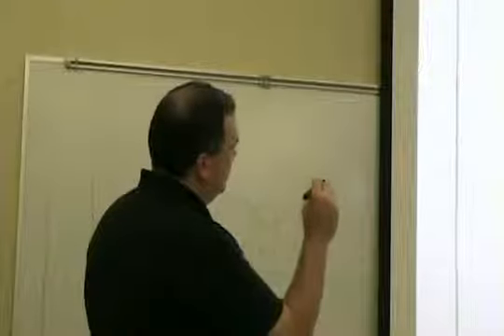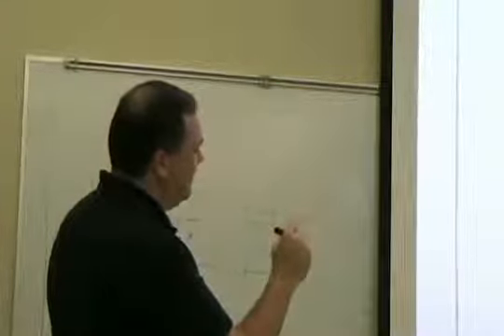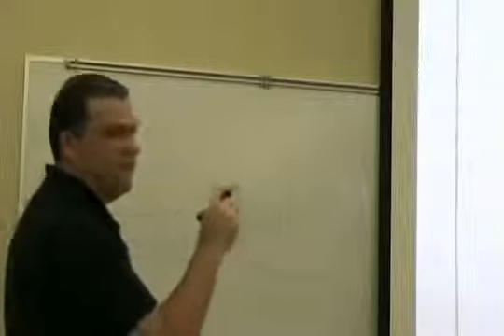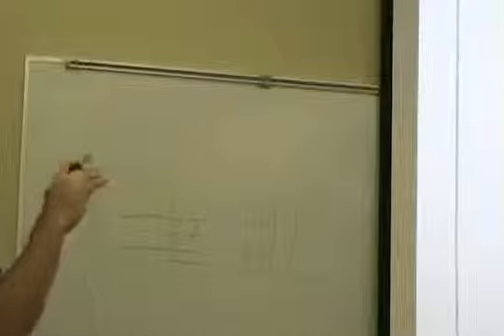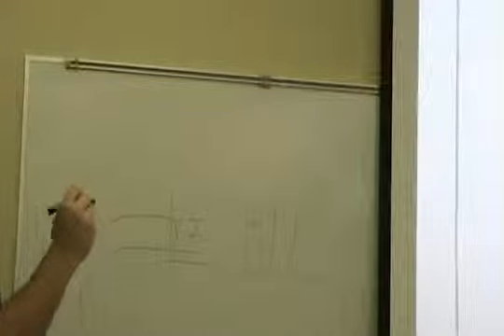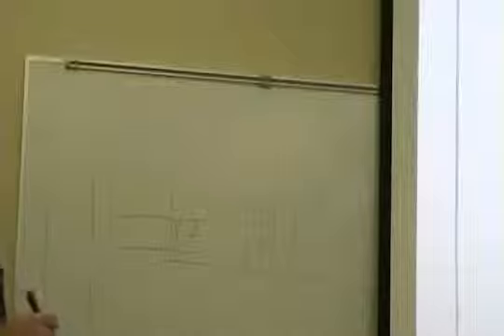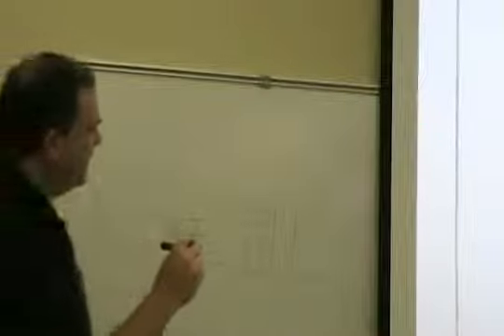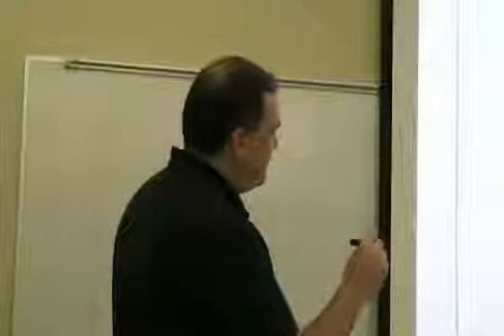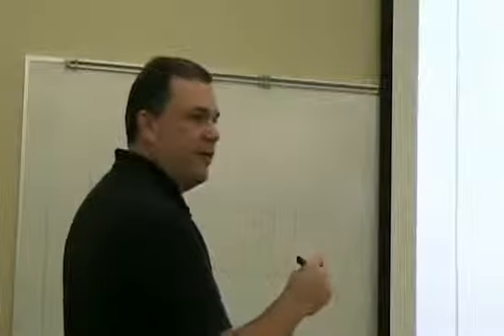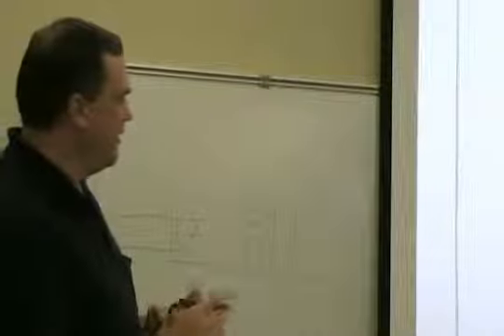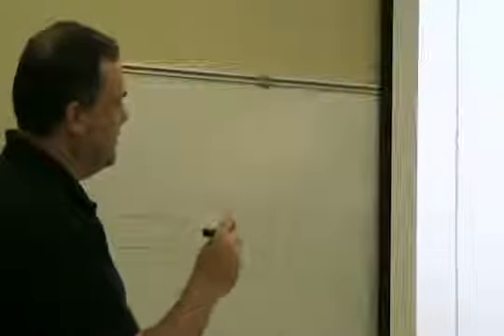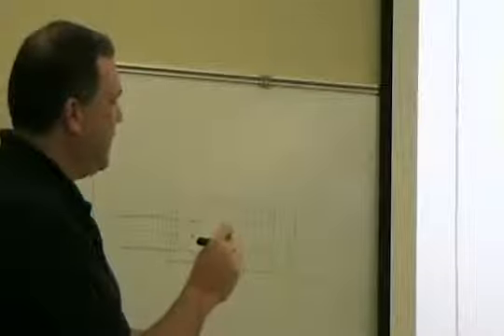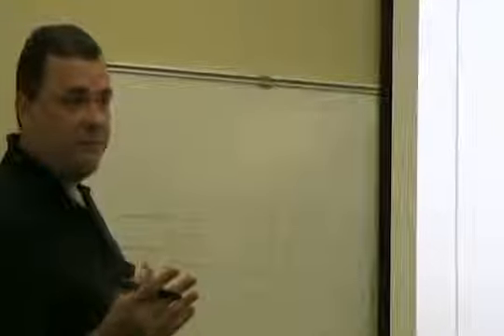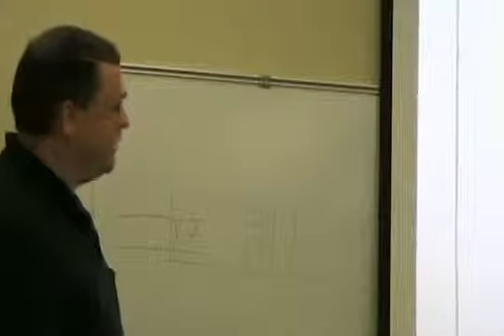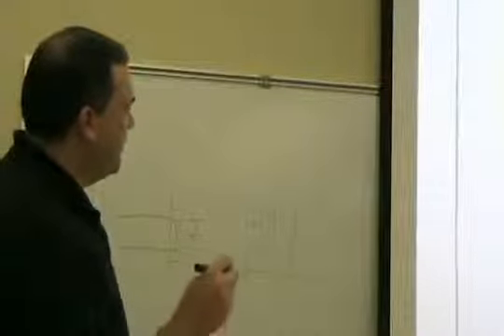These dash lines here just show our air tubes that we run down to this airflow sensor. And there's a static pressure, differential pressure transmitter built into this box that actually reads that velocity pressure. Next thing down the line here is our reheat valve and actuator. We're normally going to supply that reheat valve, and we're going to put an actuator on it, tie it back to the DDC, it's ready to go. Again, every actuator has the possibility of having different motor timings. We've got to know that to make sure we're putting the right motor timings in the box, in the DDC.